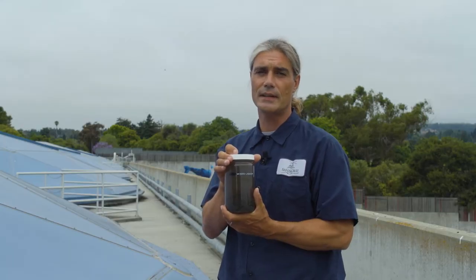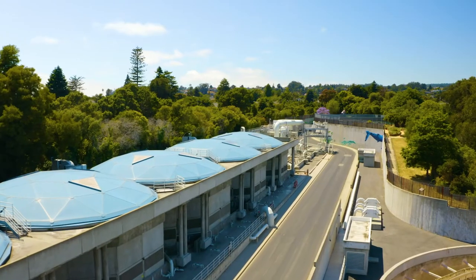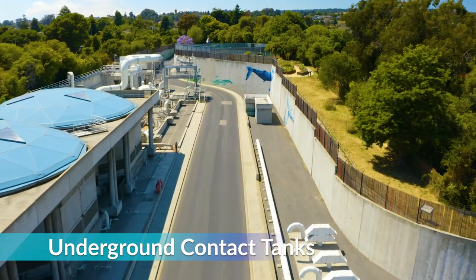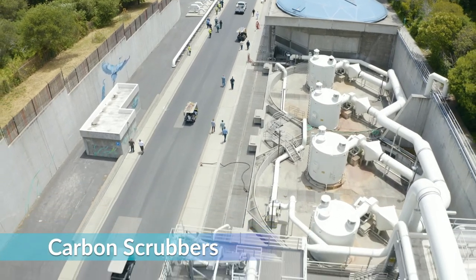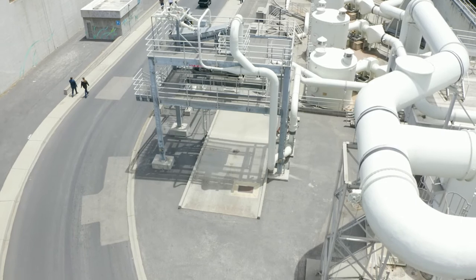Here's a sample of what the wastewater looks like now. This is called mixed liquor in the industry — although I assure you there isn't any alcohol here. The microorganisms are the brown material. Once the water exits the trickling filters mixed with sloughed off microorganisms, the flow enters two solids contact tanks in a serpentine lazy river type of channel with diffused air pumped in on the bottom. The diffused air prevents the microorganisms from settling out and the gentle agitation allows them to bump into each other and stick in order to create larger clumps of material that will settle out easily in the next tank. All of the foul odors from the trickling filters are pumped over to these carbon scrubbers for foul air treatment. In an effort to be good neighbors we have added extra vapex units to help as well. These vessels hold activated carbon generated from coconut husks which absorb the organic particles from the foul air before it is released into the environment.